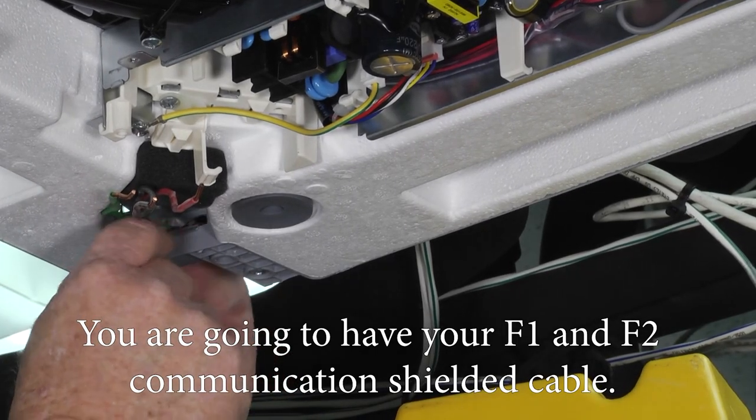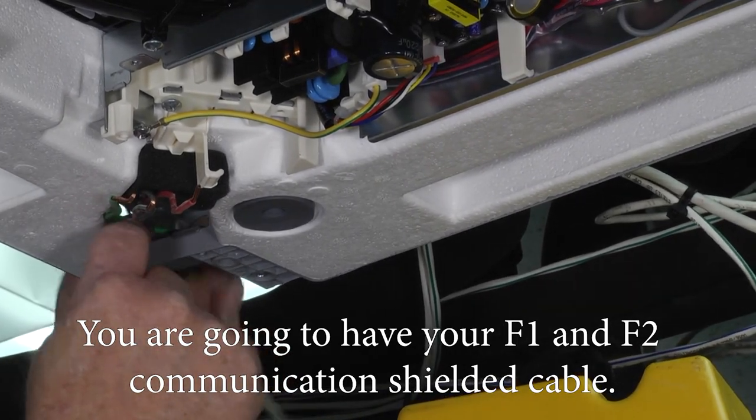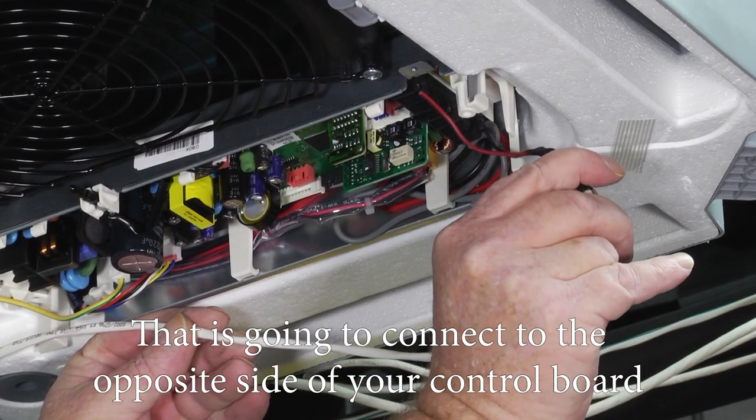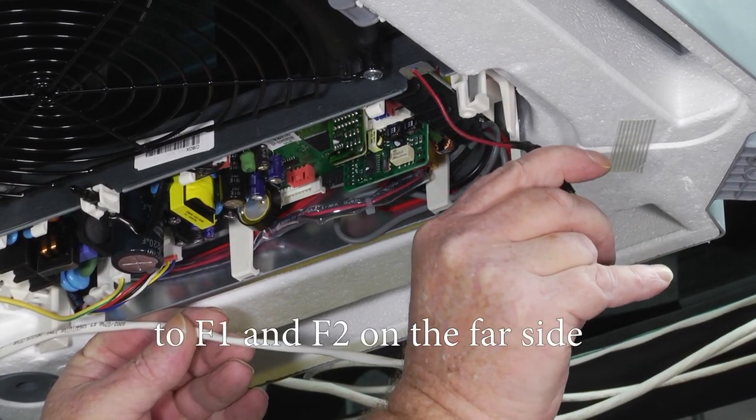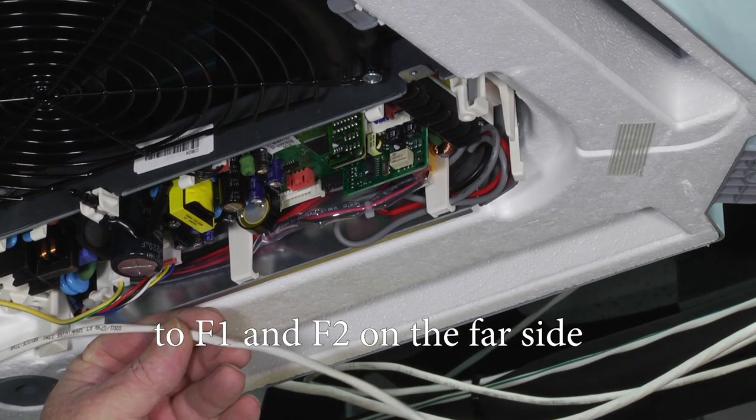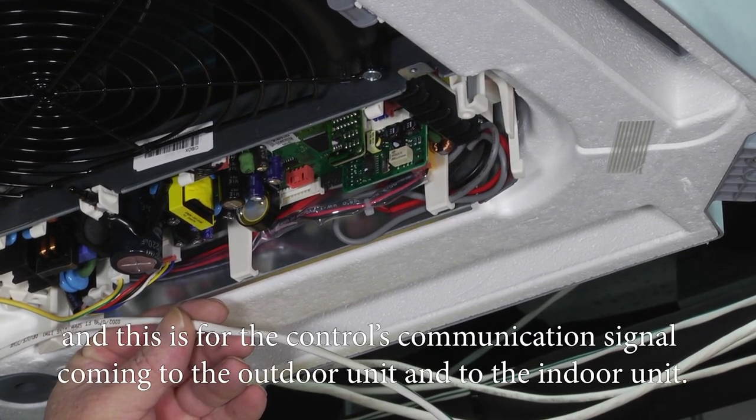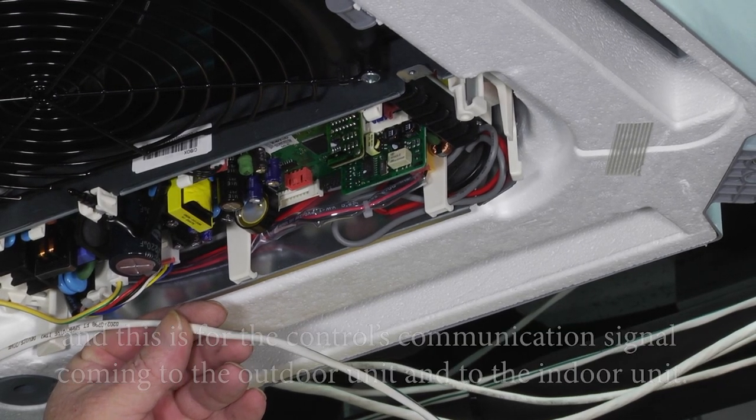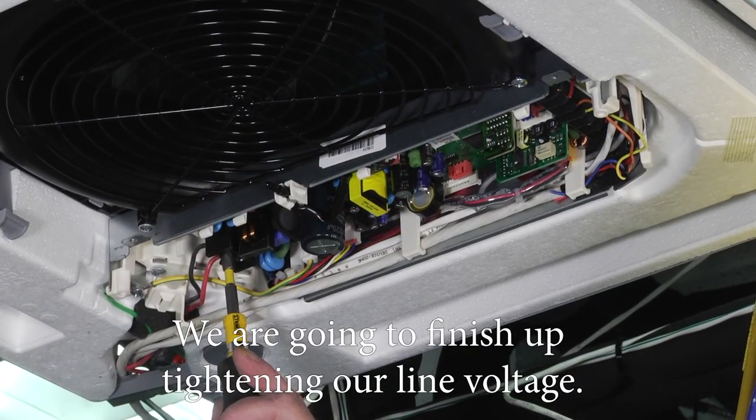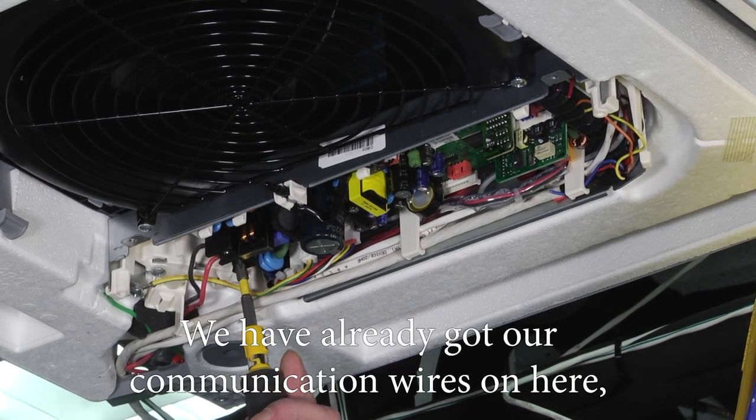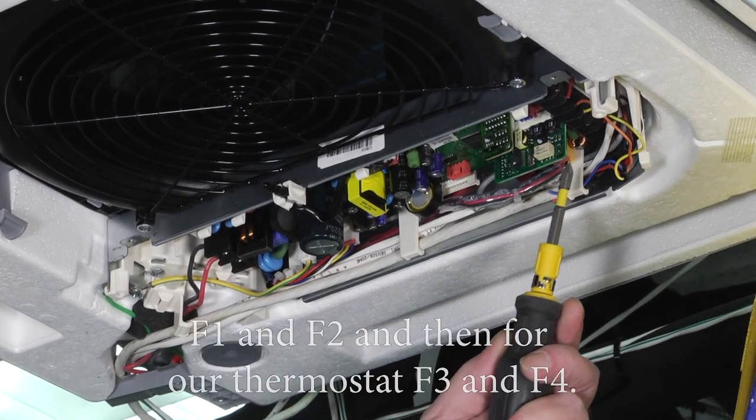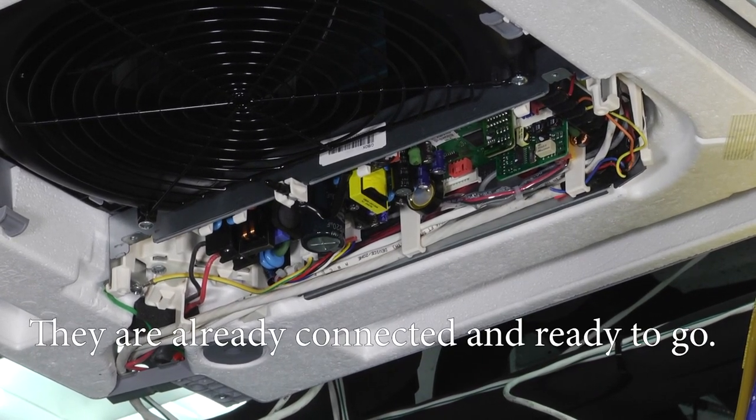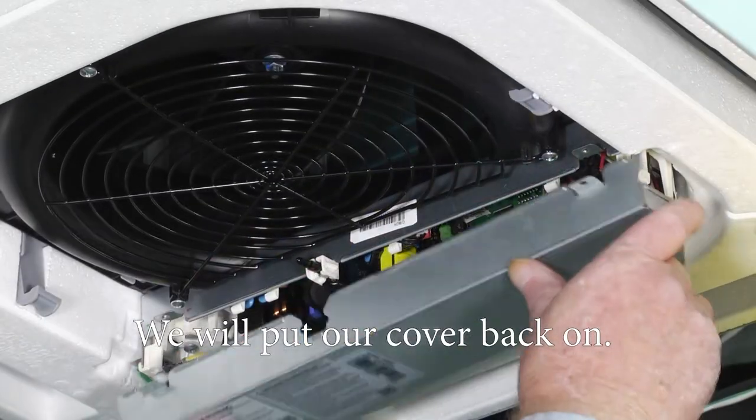You're going to have your F1, F2 communication shielded cable. That's going to connect to the opposite side of your control board to F1, F2 on the far side, and this is for the controls communication signal coming to the outdoor unit and to the indoor unit. We're going to finish up tightening up our line voltage. We've already got our communication wires on here, F1, F2, and then we'll put our thermostat F3, F4. They're already connected and ready to go. We'll put our cover back on.